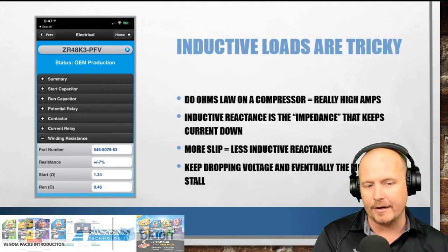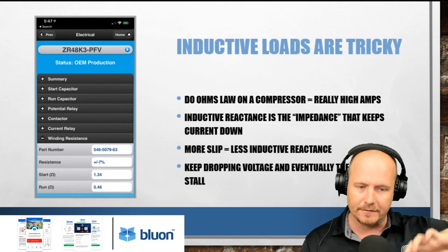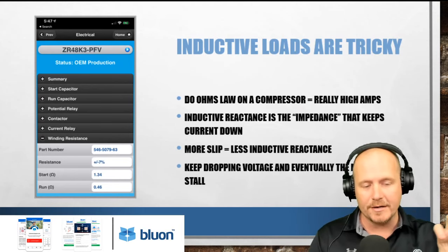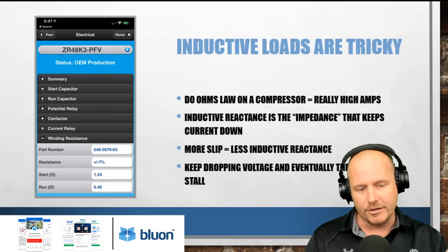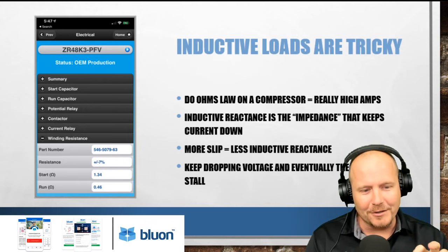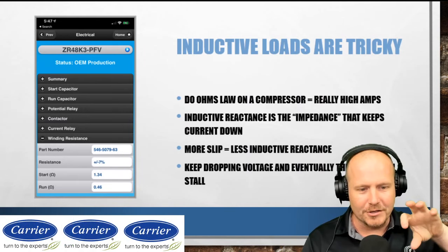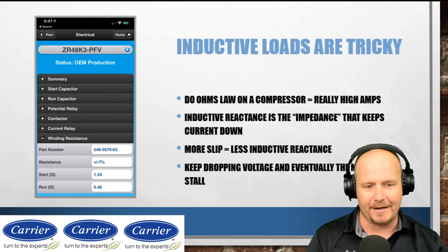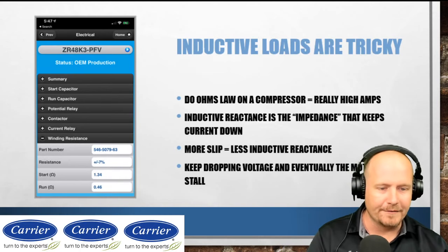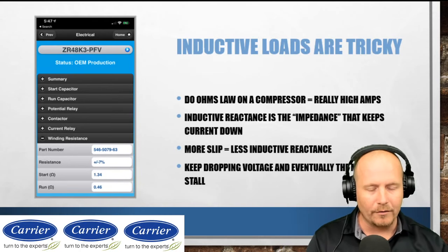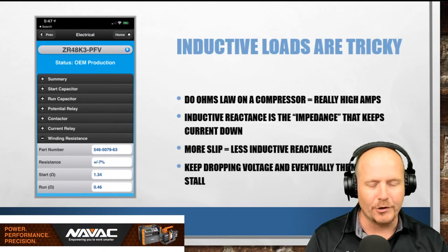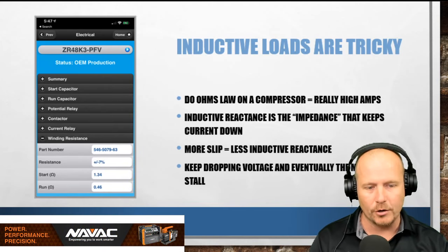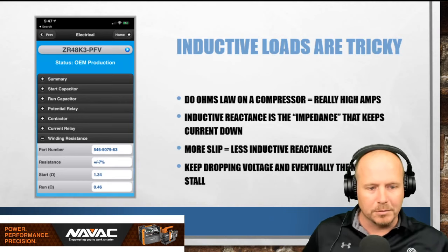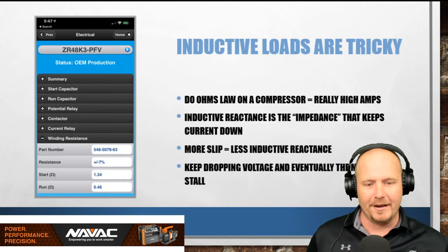But it's not linear like that, because as you're decreasing the voltage, you're also decreasing the inductive reactance, which in turn means changing the voltage on a motor, you're dialing the voltage back and you're dialing the resistance back at the same time. So inefficient, they don't run well, they're not doing the job they're supposed to do. That's from a very practical standpoint. So the answer is don't apply voltage that's lower than a motor's designed for.